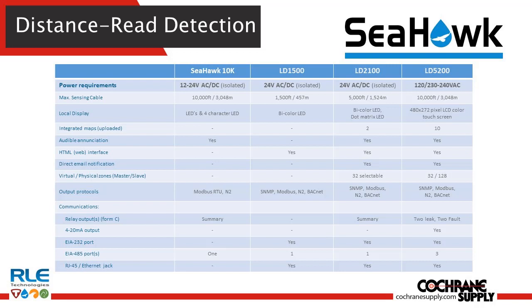The variety of different controllers that exist inside of this space is the Seahawk 10K, the LD1500, the LD2100, and the LD5200. As you can see, there's a variety of different max sensing cable lengths available, all the way up to the LD5200, which will do 10,000 feet of sensing cable.